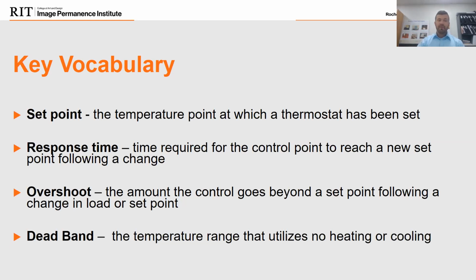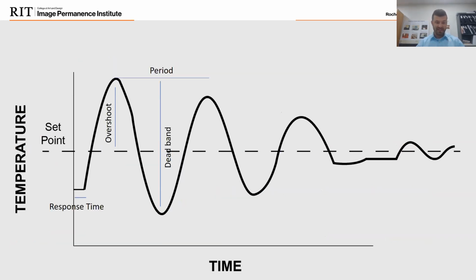So going back to the vocabulary here, the set point is the temperature at which the thermostat has been set. That's when we all talk, I need 70 degrees. That's the set point we're aiming for. The response time is the time required for the control to reach a new set point following a change. An overshoot is the amount the control goes beyond the set point following a change in load or a change in set point. And the deadband is the temperature range that utilizes no heating or cooling. So I wanted to find a way to really almost display these, and I think this is the best example I could find to show exactly what is meant when someone discusses overshoot or deadband or response or set point.